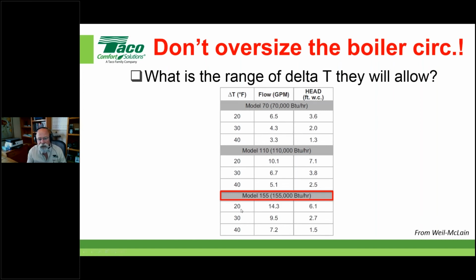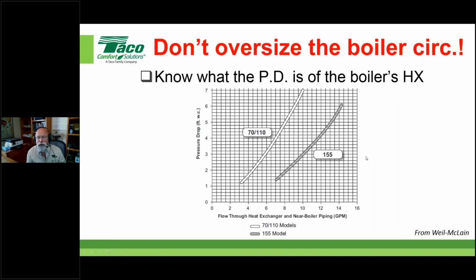So in this case, they're showing you a 20 degree, a 30 degree, and a 40 degree delta T, and they're giving you the following information based on that. What to expect for flow, your initial thing you need for sizing a pump, and then what to expect on the pressure drop through the near boiler piping and the heat exchanger in this case. So, I'm going to show you what that looks like. These are the charts we're talking about. This is what you need to be able to comprehend and understand, and how to interpret this, okay?